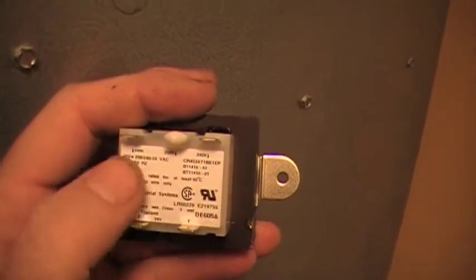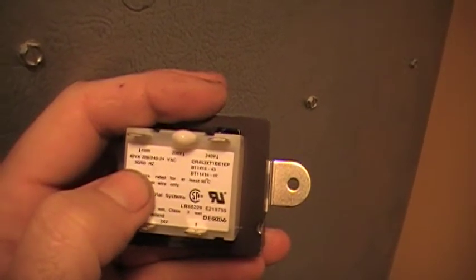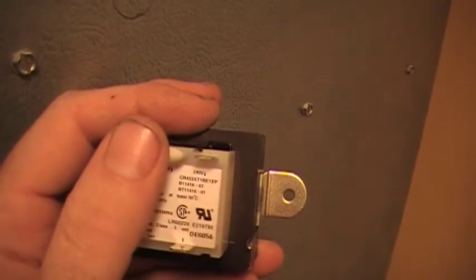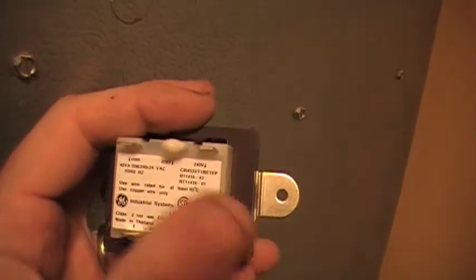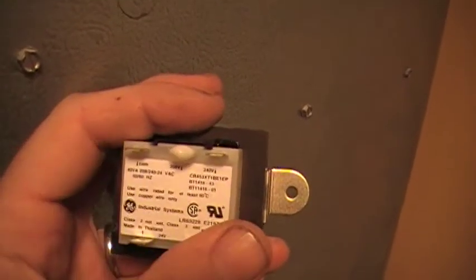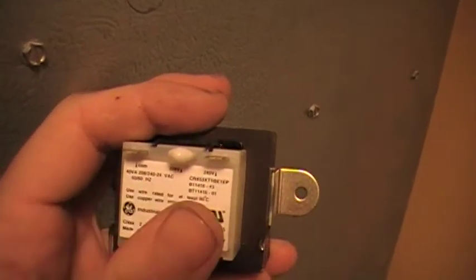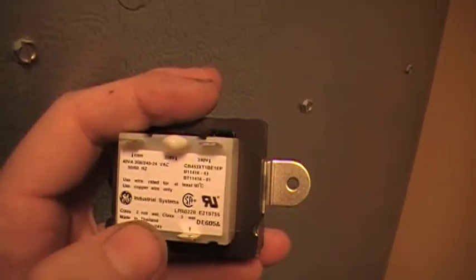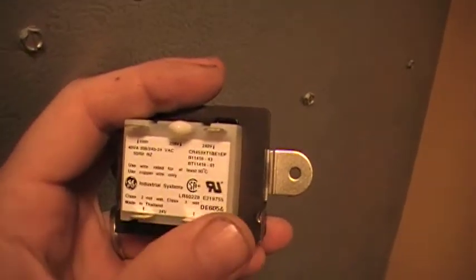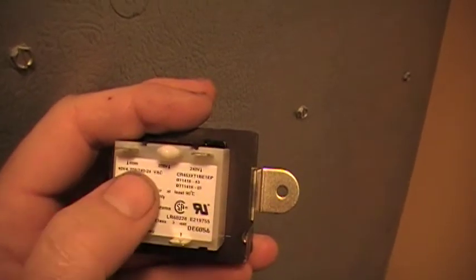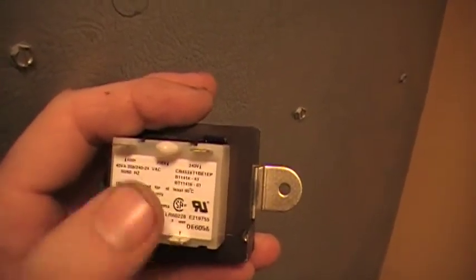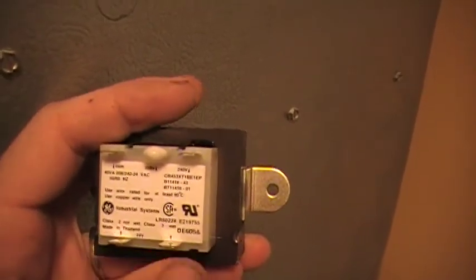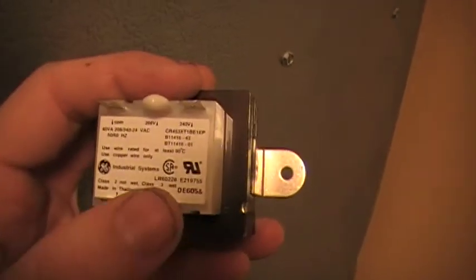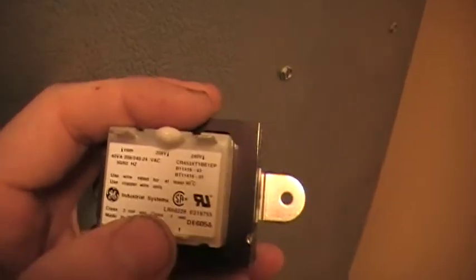And this is a 40 VA, or volt amperes. Basically, it's a step-down transformer, and it's going to take 240 volts AC and put it through here, and then create a much lower voltage, 24, so that you can use it for your controls. And just as a reference, the ratio between this winding and this winding is going to be 10 to 1. This little fella right here, if it goes out, you got nothing, because all your controls that kick on your compressor and your fans and everything are supplied by 24 volts AC, and here's where it's made right here.